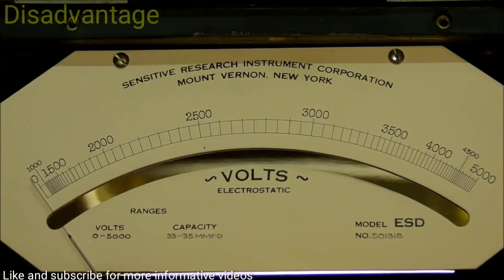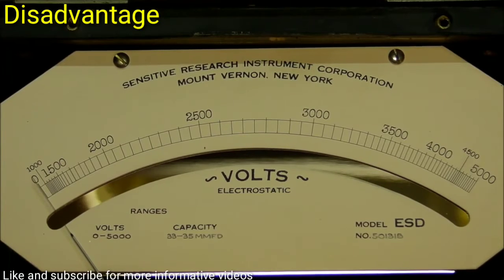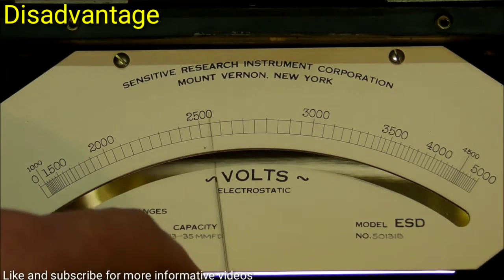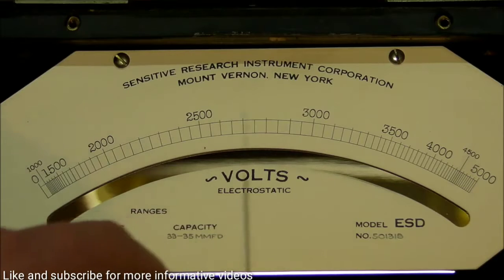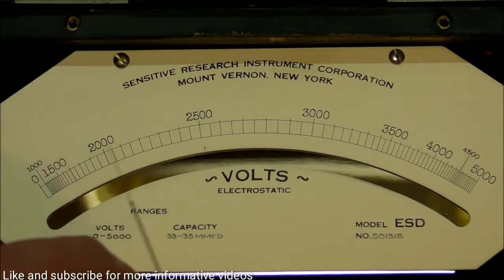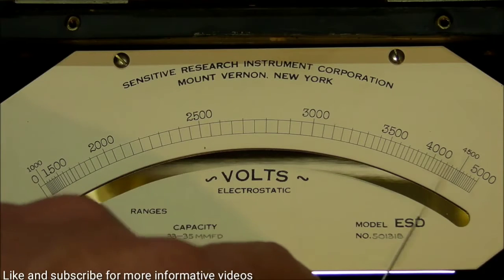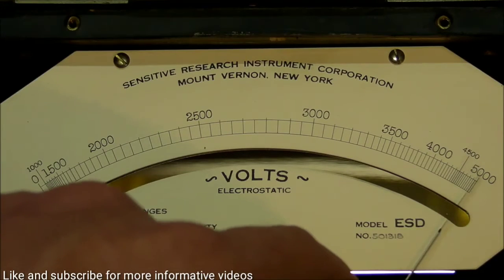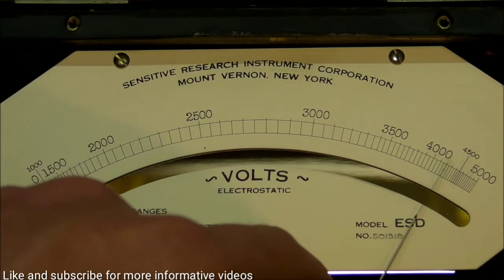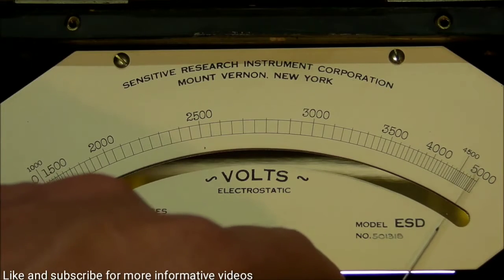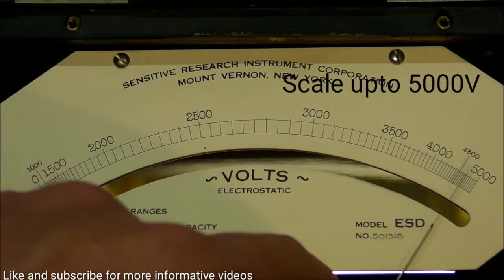There's an electrostatic force that just pulls it ever so gently over that way across the range of the meter. Now, one disadvantage of this kind of voltage measurement is that the scale is really non-linear. Up here in the middle of the scale, we've got pretty good deflection of degrees per unit volt going into the device. And even up here at the top of the scale, we've got 5,000 volts and 4,000, 5,000 volts. It's a pretty decent scale up there.